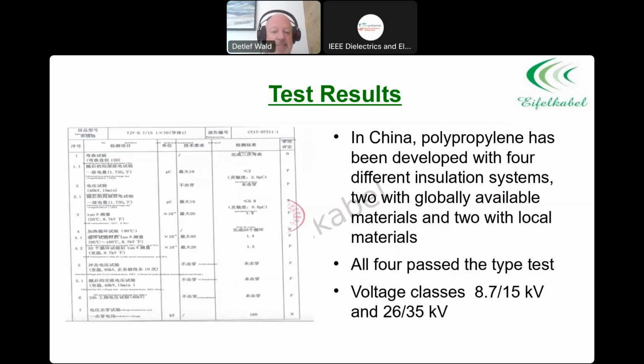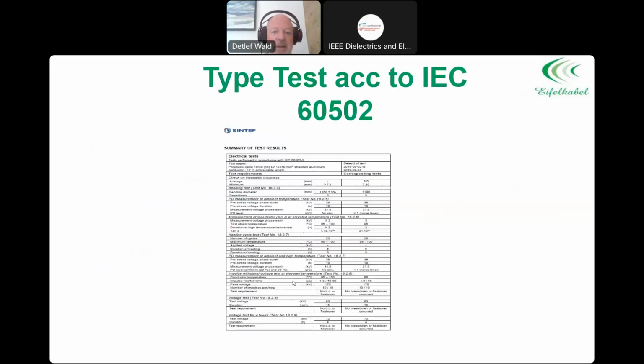Looking at type test results, here you have China. Certain people are able to read that perfectly. For the people who are not so perfect in Chinese, there's an English translation below. In principle, the most important thing you can look at is the P, P, P, P, P, P, P, or non-applicable. So the test passed the application for a 15 kV cable. And here, more interesting, the electrical type test according to IEC 60502. And here I also show you the results, and it passed the type test perfectly.